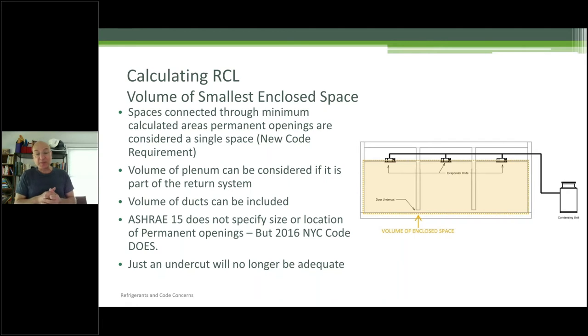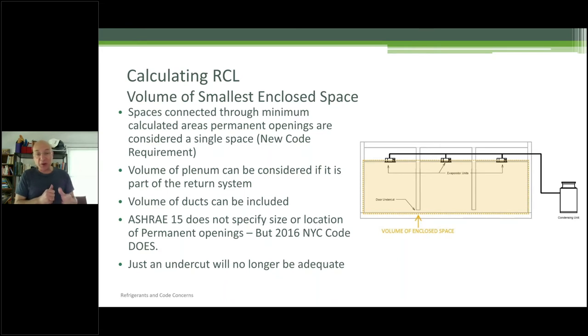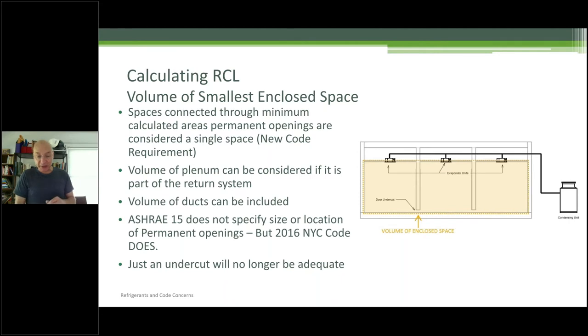The 2016 New York City code — coming very soon — does specify size and location of permanent openings. We worked very hard on finding a good scientific way of dealing with this to take away all the uncertainty from designers. Just an undercut will no longer be adequate. Why? Because you need an air makeup system. If the refrigerant escapes — 410A and CO2 are both heavier than air — if there's no makeup, nothing's happening and the refrigerant is not going anywhere. That's why an undercut alone is not adequate.